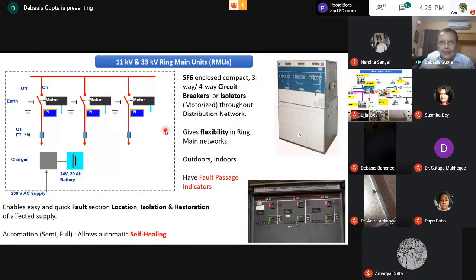So let's talk about the isolators or breakers. If these are isolators and you want remote switching on and off, you attach a motor, controlled through an RTU, remote terminal unit, or more commonly an FRTU, a feeder RTU. It's a small RTU with maybe a few dozen IOs, analog inputs and digital outputs, and through it you can control these motors and switch on or off remotely.